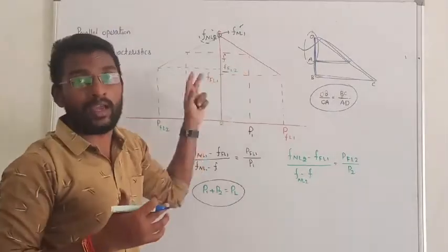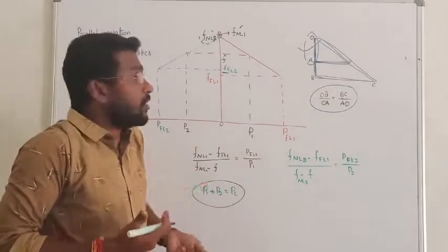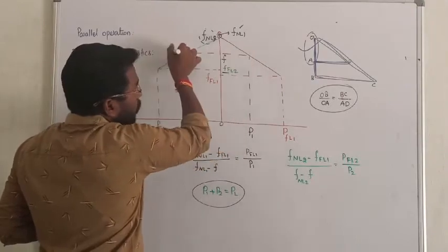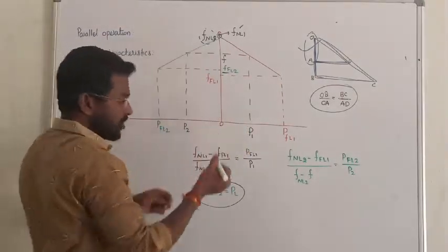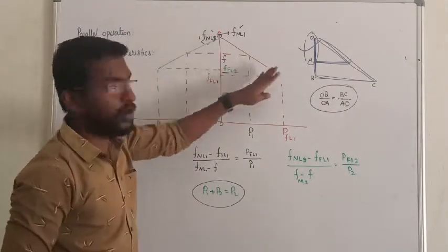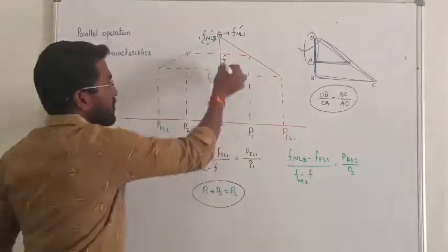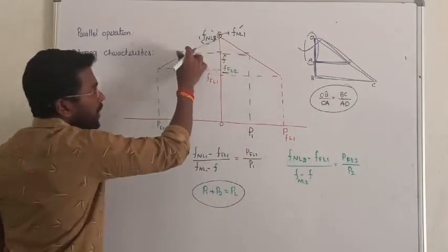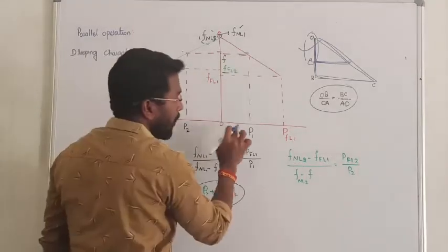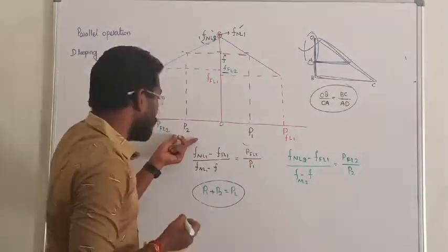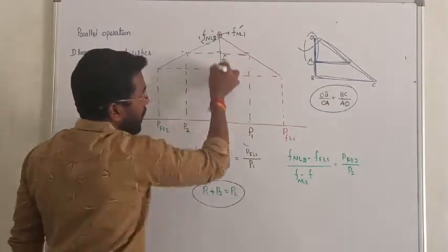Sometimes P1 and P2 are given together and you may be asked to find the corresponding frequency. We have to maintain the frequency as constant. The frequency offered by those two alternators in parallel must be the same. There is a large triangle and a smaller triangle. The power shared by alternator 1 and the power shared by alternator 2 are determined using this triangle ratio.